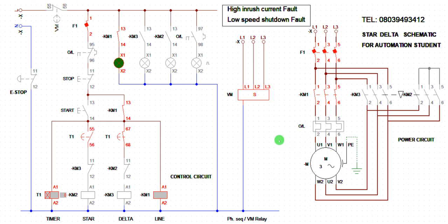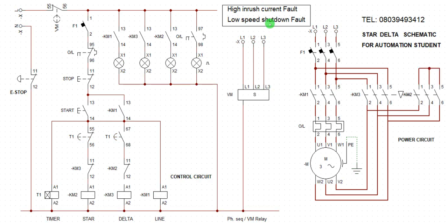This is where the design is wrong. You are not supposed to experience these two faults. We should not experience high in-rush current because we have low speed before high speed. The star contactor is supposed to be a priority — a master contactor. If the star contactor is not energized, the line contactor and delta contactor should not get energized at all. If the star is not closed, delta and mains shouldn't energize in the first place, because doing otherwise is not good for the motor.